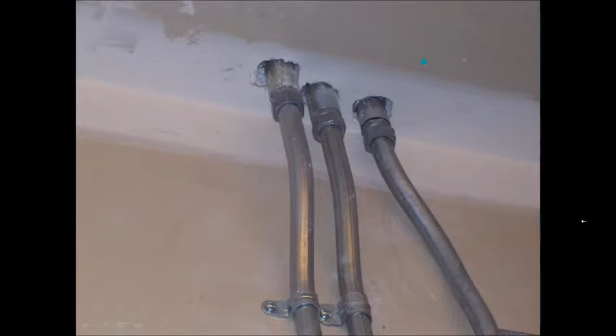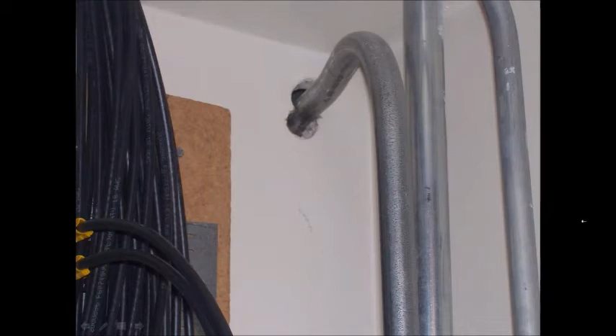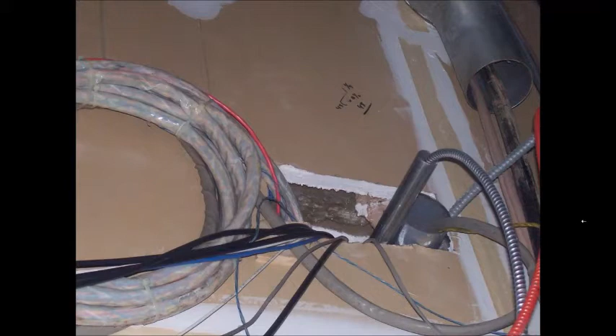Don't prop them open, and don't get all uptight because the nasty fire inspector or the mock surveyor like me has got an issue with it. We need to contain fire and smoke, and that's why this is a common deficiency that we see. Penetrations in walls, in ceilings, in fire-rated barriers need to be protected to contain and confine the products of combustion. And when we see everything from the kinds of things that you're seeing on your screen, fire and smoke is not going to be contained in an area of origin like it's designed to be contained in accordance with the codes, NFPA 101, NFPA 99, and all the relevant related codes.